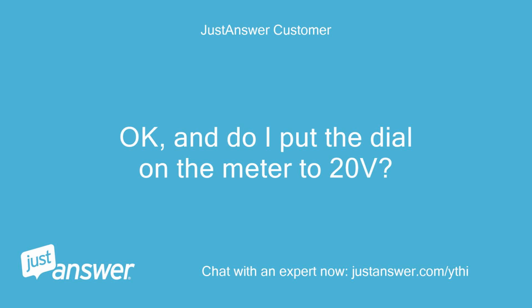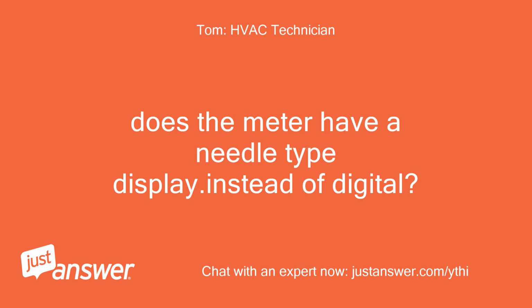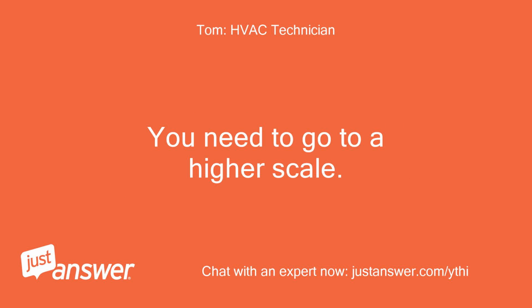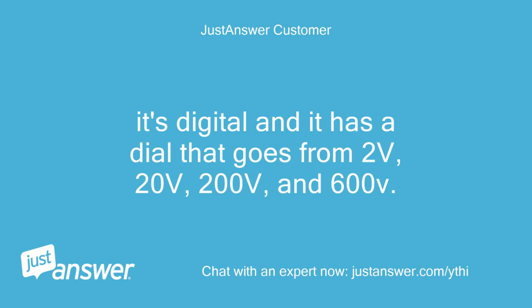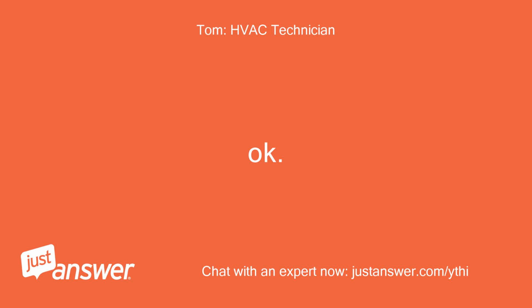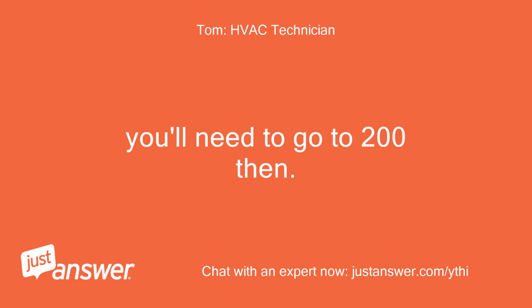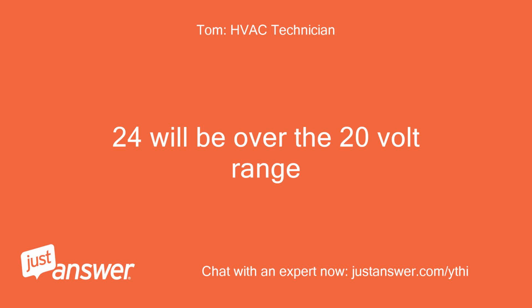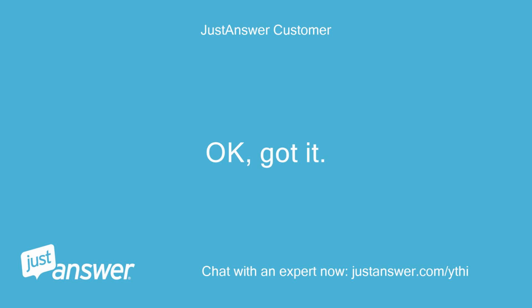Okay, and do I put the dial on the meter to 20 volts? Does the meter have a needle type display instead of digital? You need to go to a higher scale. It's digital and it has a dial that goes from 2 volts, 20 volts, 200 volts, and 600 V. Okay. I see. You'll need to go to 200 then. 24 will be over the 20 volt range. Okay, got it. Back in a bit. Okay.